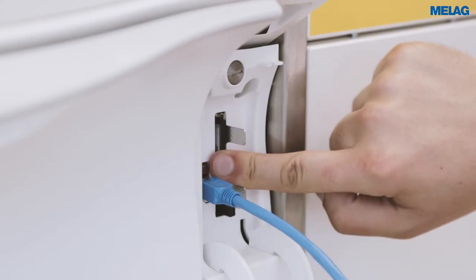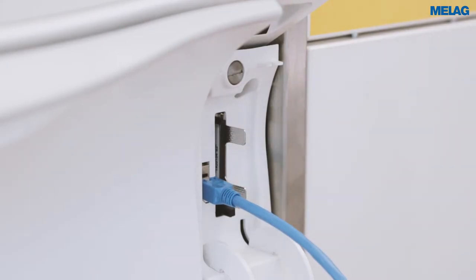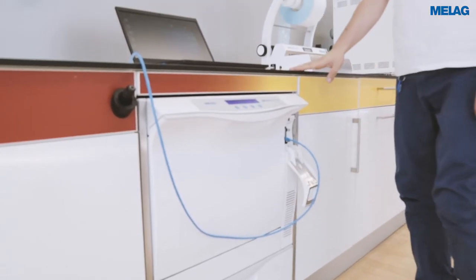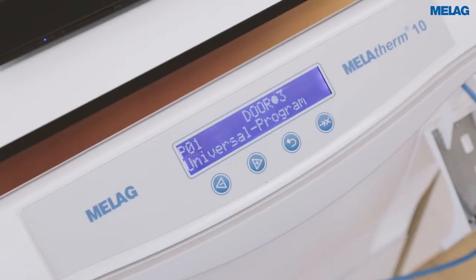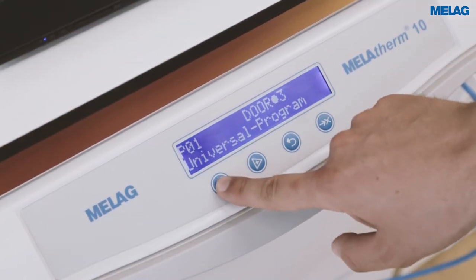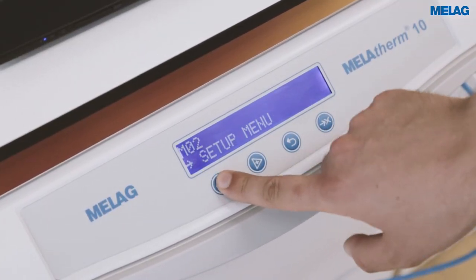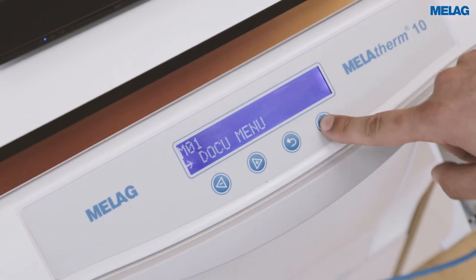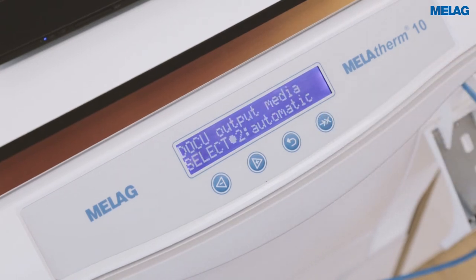To transfer log files from the MELAtherm 10 to a CF card or network, we need to enter the docu menu. To enter the docu menu, press the minus button two times, and if you see the docu menu, confirm it with the fourth button to the right side.